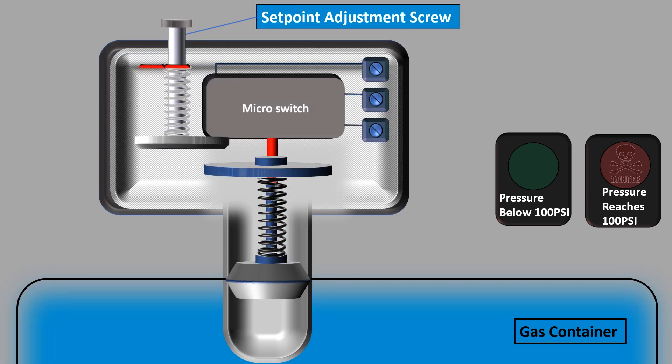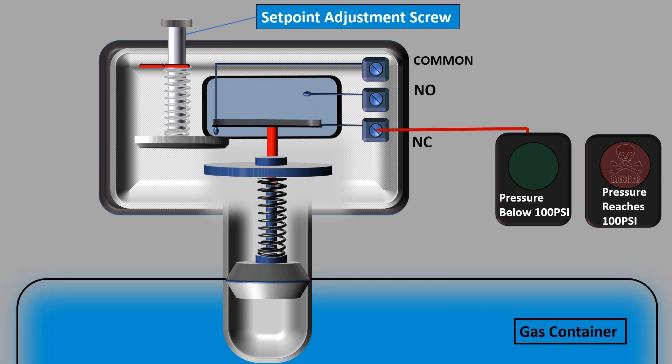Now we wire green light to normally closed (NC) terminal of the switch and red light to the normally open (NO) terminal of the pressure switch. Power is connected to the common terminal of the switch. The inlet pressure from the container is applied to the bottom of the operating piston.